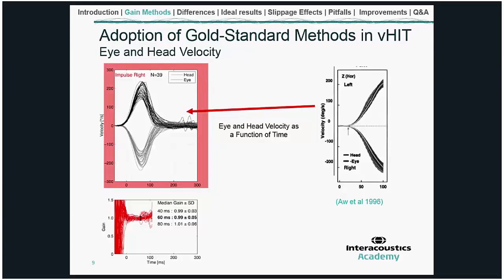One important aspect is that we try to enlarge the traces as much as the space on the report allows, giving a zoomed-in version of the velocity traces. This zoomed-in presentation helps more easily identify artifacts such as noise or slippage. With a smaller presentation of eye and head velocity traces, there is a tendency to hide artifacts, which we want to avoid.